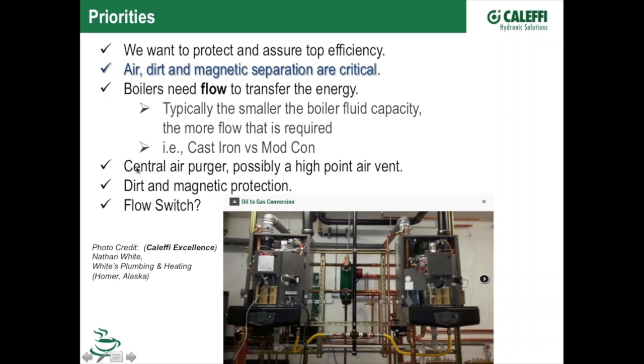We'll talk about the central air purgers. Every system should have an air purger at the equipment. And I keep saying heating, but this would apply for a heat pump also. We'll talk probably more about that in the next month's session. I consider that more of a renewable energy. Dirt protection, magnetic protection, possibly a flow switch, to drop out the boiler if there's a condition where we don't have flow going through the system.